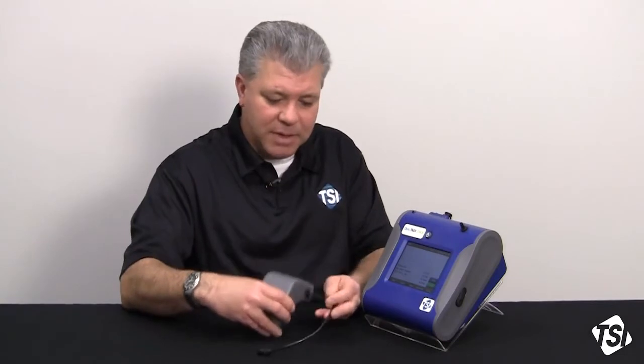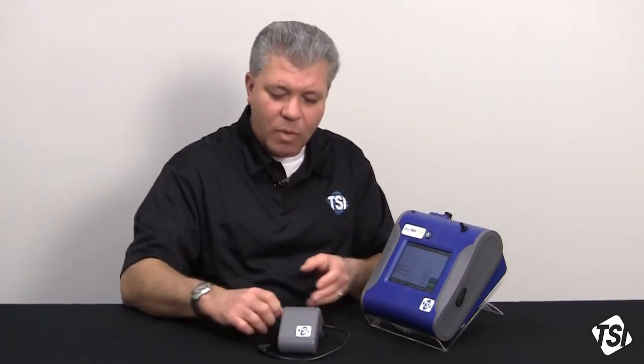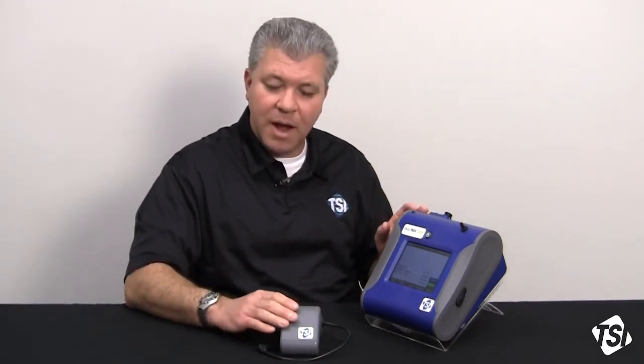A couple of things to keep in mind. For a 24-hour sample, people will typically set their Auto Zero module frequency at, say, 2 hours, 3 hours, 4 hours, sometimes 6 hours, so that you're getting it fairly regularly during the day.